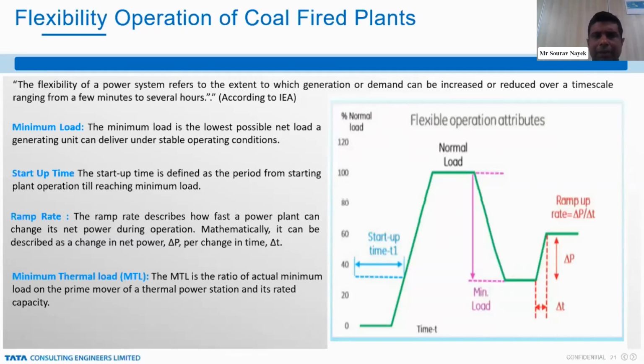The flexible operation of the power plant is the reduction of the generation according to the demand, to maintain the RE source and the thermal power source in a balanced way. And this thermal power plant has to be taken to the minimum load. The minimum load is the lowest possible net load of a generating unit which can give a stable operating condition. Now, startup time we have also defined. The startup time is defined as the period from starting plant operation till reaching the minimum load.